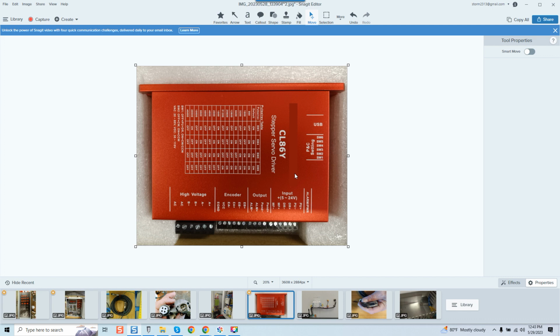Now, once again, just to clarify, because I get guys that'll say, you know, which is better? Better in terms of what? And that's what I always say. If you're looking at more accuracy, a stepper or a servo system have the same accuracy. It's the depths at which they achieve that accuracy is different. Now, if you say which can be self-correcting with accuracy in the event the motor is manually pushed out of position or pushed above its operating envelope, either one can be pushed above their operating envelope to actually make them lose steps. The question is which one is aware of it? And a stepper is not aware of it, whereas a servo is because of the encoder. So that's the best explanation on that. I feel that really just differentiates the two types.